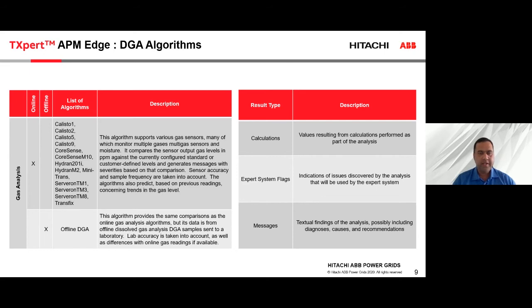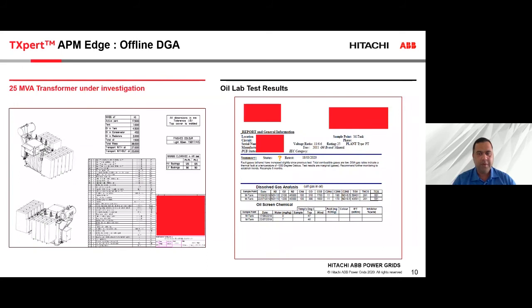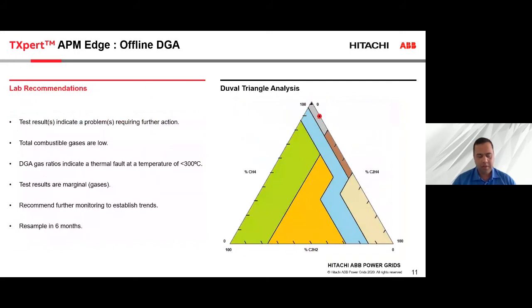Now, in this case study, we investigated a 25 MVA transformer. We got the oil test lab results, and the test report told the end user that there is some problem which requires further action. Gases are low, DGA ratios are showing a fault temperature of less than 300 degrees, results are marginal, and they basically recommended please resample in 6 months' time.